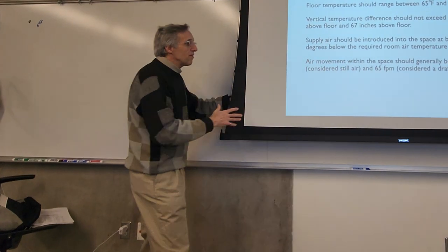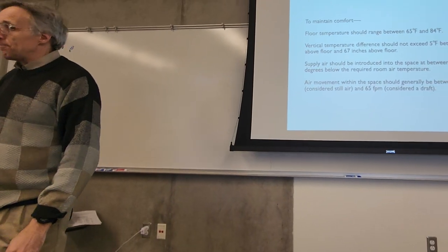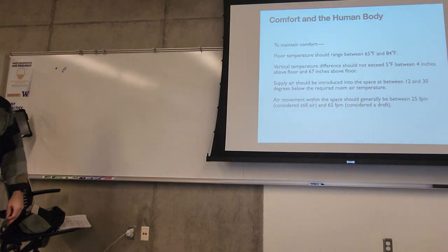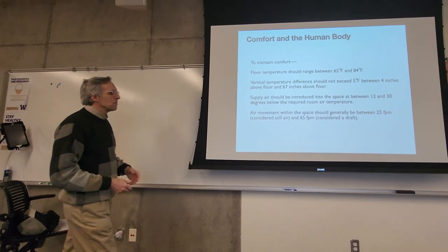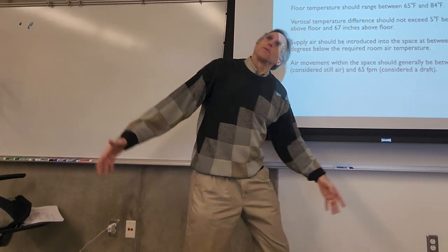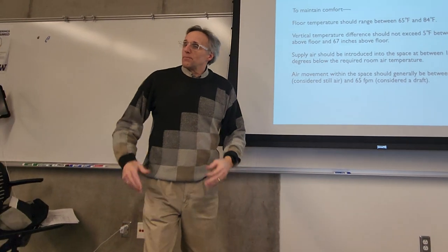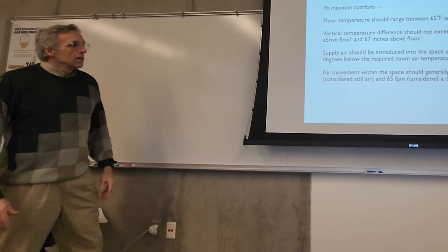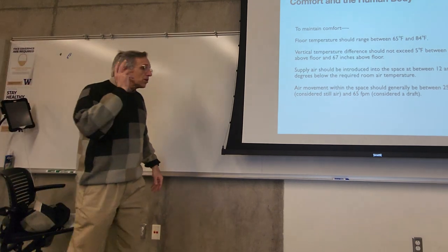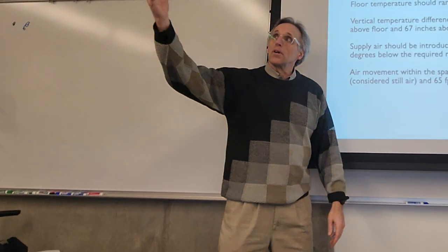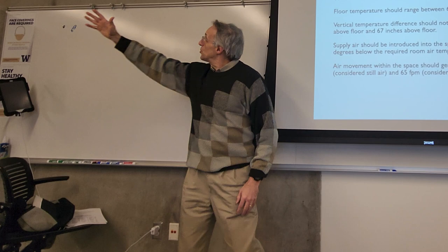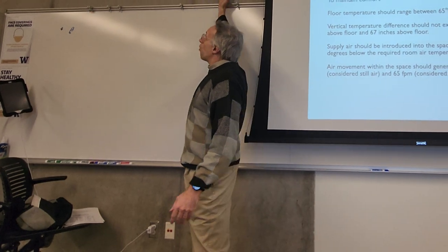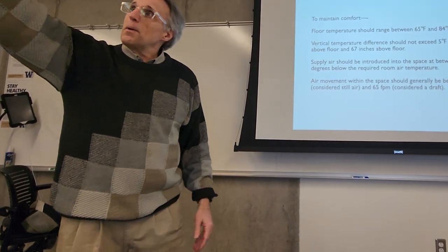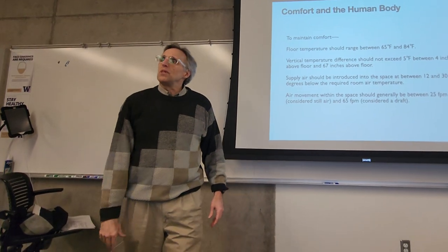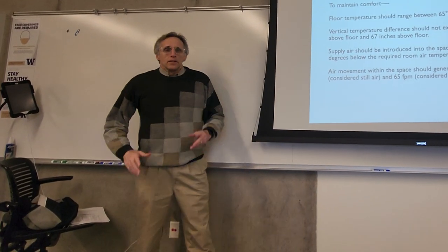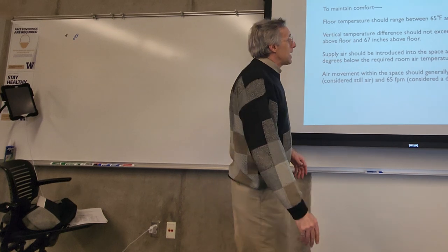Generally speaking, 25 feet per minute is considered still air. Anything below 25 feet per minute is still, and if you go a little higher than that, to 65 feet per minute, then people are like, wow, man, it's really uncomfortable in here. 50 feet per minute is a good average velocity for when you come out of a register. So you've got air coming out of the wall here, and by the time it gets to the middle of the room, somewhere around 50 feet per minute is a good velocity that you want it to be at.